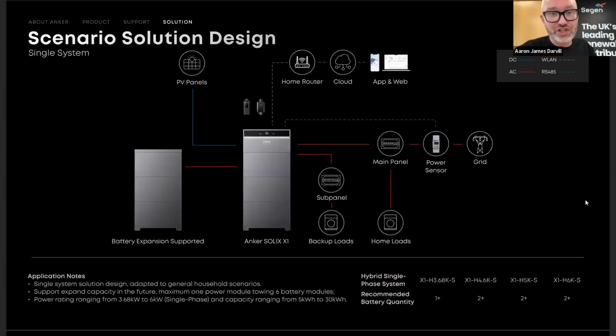Let's give you some scenario solution design, which will all be sent to you and is on your Anker Academy. We'll show you simple structured designs, like the single system here, where you have your typical Anker Solix 15 kilowatt hour with your power module, and then to the left or right, whichever suits, you can add stackables for more storage. You need a 300mm clearance between the next stack of batteries, on either side and at the top. No clearance is required at the front of the battery. The reason you need that 300mm clearance is to get a screwdriver in — we've had issues before where it was complicated and we had to find a very small screwdriver to sort it out.